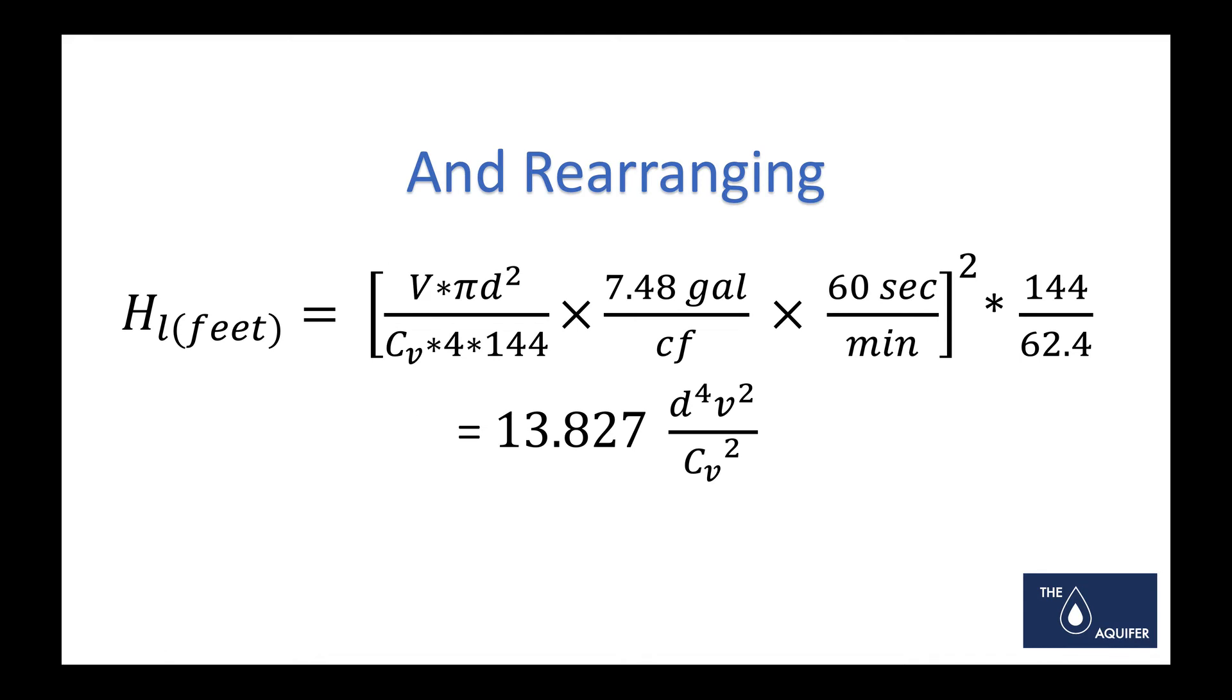Now we're going to go ahead and we're going to solve those equations for head loss in feet. Doing a lot of math and algebra here, we're going to come up with the relationship between head loss in feet and the diameter, the velocity of the flow, and the Cv. We've got this 13.827 factor out front, which is basically the product of pi and the numbers that are not variables here.